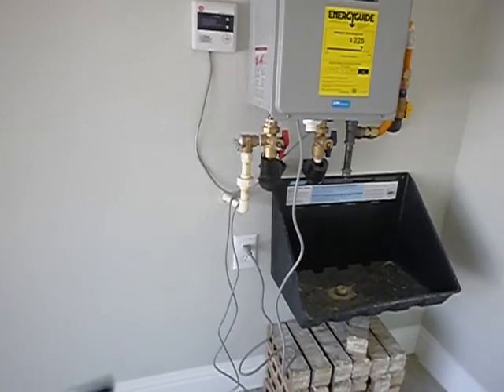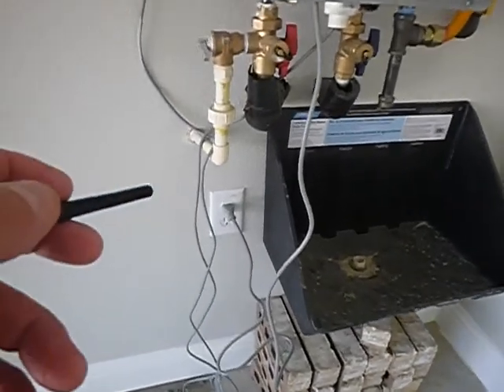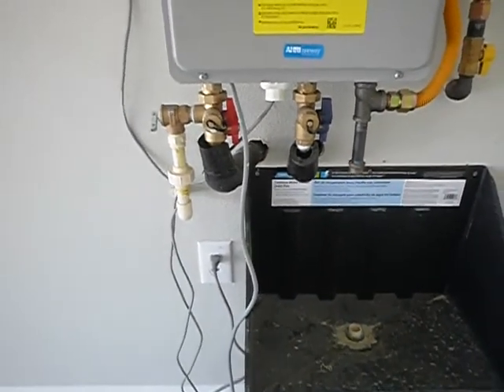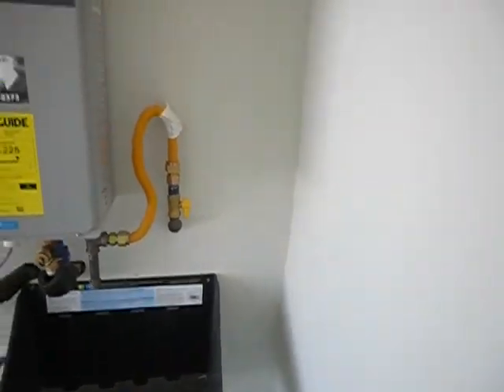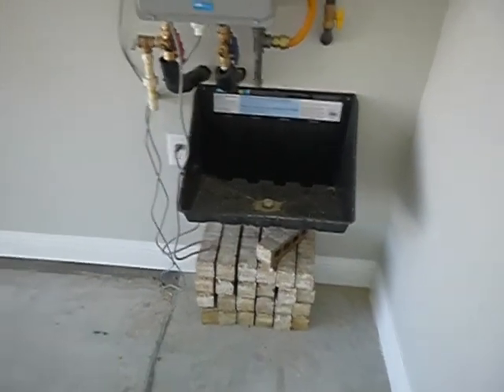But with or without the drain and vacuum breaker and so forth, really, it'd be nice. And I don't see how they're going to do that. You've got an electrical receptacle right over here, right? Underneath all this water. And there's nothing against that, it's just not real smart. But really, moving this pan would be easy enough, except that you can't. So the answer is probably moving the whole system over 6-8 inches. Kind of an interesting dilemma there. I don't know. We can find some way to work around it, I'm sure.